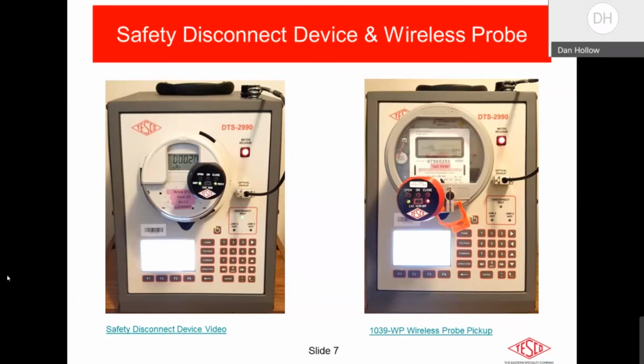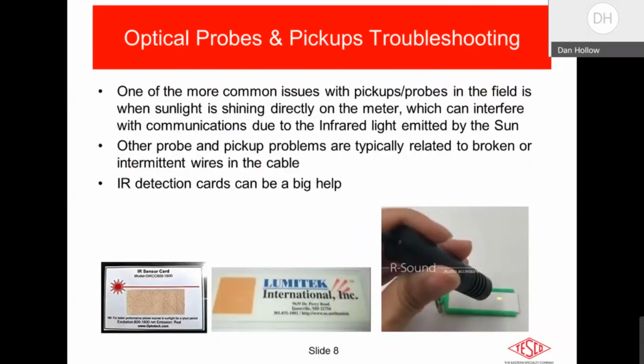So let's go ahead and move on to the next slide. Optical probes and pickups troubleshooting. This was something that was kind of a last-minute suggestion by Andy, and she was very correct in having me address this. A lot of times people can't communicate with their meter optically, and they don't know where to start. So what do I do? I can't talk to the meter optically. Is it the meter? Is it my optical probe? Have I incorrectly configured the vendor's software and I'm using the wrong port?